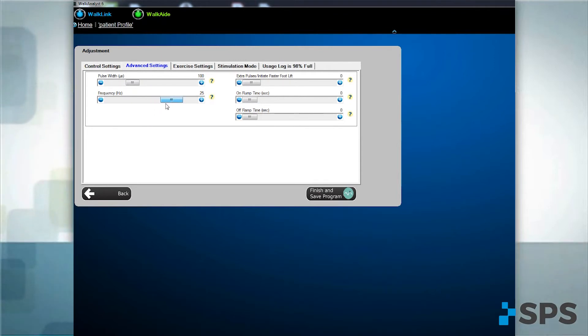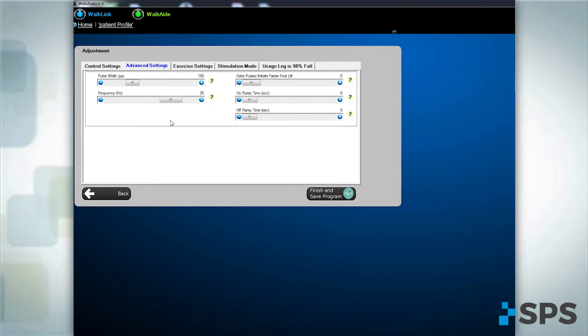Increase the frequency of pulses. It often improves comfort. For example, PEDS, small limb, hypersensitivity.